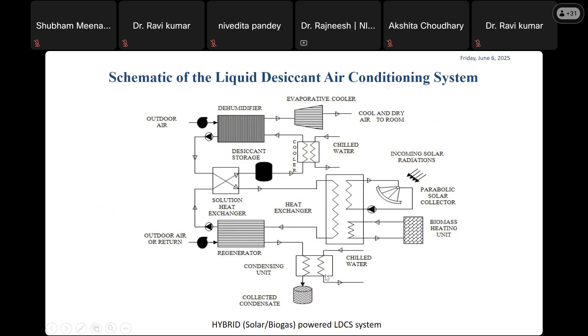Now heat energy is coming from two sources. One source is the ETC, the evacuated tube collector. In addition, an alternate arrangement of biogas is provided. We have used a 2 cubic meter biogas plant, and the heat energy is stored in a hot water storage tank. That hot water is supplied to the regenerator and used for the regeneration purpose. Additional cooling is sometimes required, and for that an additional arrangement is provided. This is the condensate collection at this point. This is the arrangement we have done.